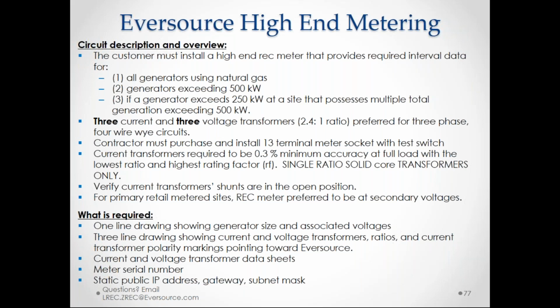So again, 3 current transformers and 3 voltage transformers are required in those cases, 2.4 to 1 ratio preferred, and again, 0.3% minimum accuracy. We always want the lowest ratio, the highest rating factor, and it must be single ratio, solid core. Again, verify that shunt trips are in the open position. For a primary metered site, for billing meter purposes, the REC meter cannot be at that primary voltage. It must be at the secondary voltage.